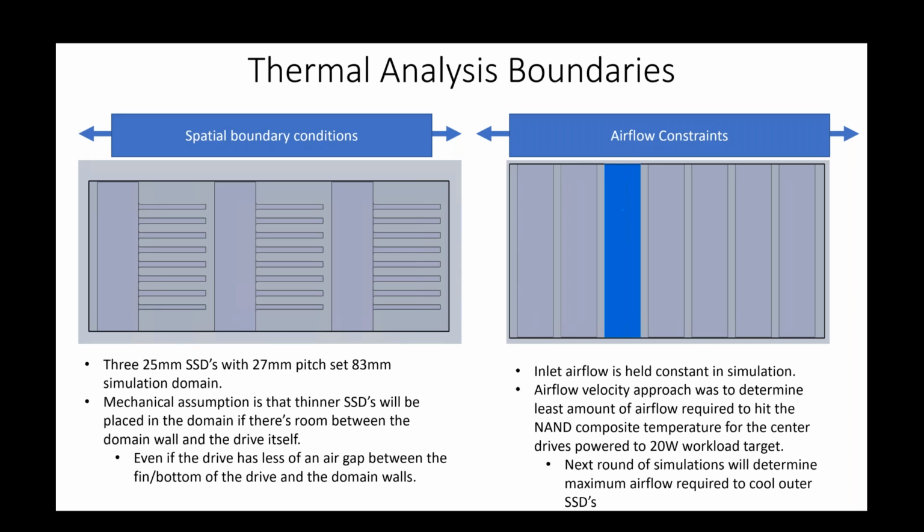For instance, I want to speak to the different tools. So for FloTherm, you may set a 50% FAR, right? But then you just have these two big bulk openings. Whereas if I use FloTherm XT, my FAR is still maybe 50%, but it's not being forced into one channel, right? I'm not getting really high CFM or really low CFM through one channel that has a block off plate or something. And so that's up to the system designer to how they want to analyze it.